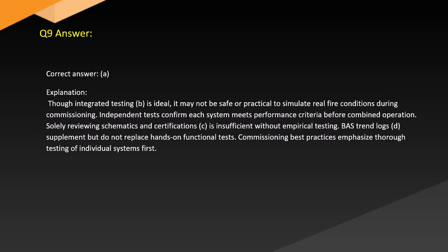Answer. Correct answer: A. Explanation. Though integrated testing (B) is ideal, it may not be safe or practical to simulate real fire conditions during commissioning. Independent tests confirm each system meets performance criteria before combined operation. Solely reviewing schematics and certifications (C) is insufficient without empirical testing. BAS trend logs (D) supplement but do not replace hands-on functional tests. Commissioning best practices emphasize thorough testing of individual systems first.